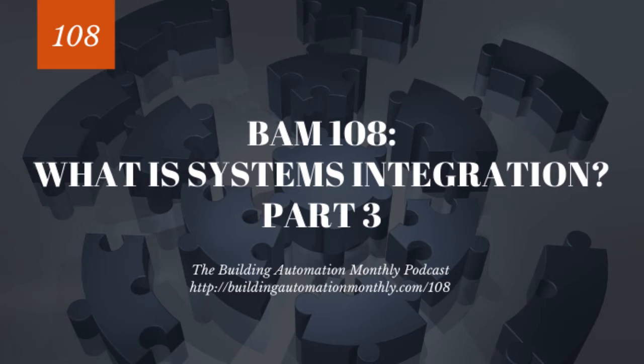Maybe you have a sum block in your supervisory device where you sum up all of the different meters and output that to a totalization point. Maybe you're summing the values of the meters and then resetting it once a month. Maybe that's what you're doing. You've got to understand what you are doing with the data in order to program the points properly.